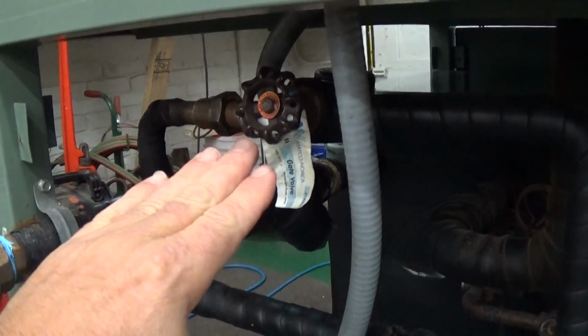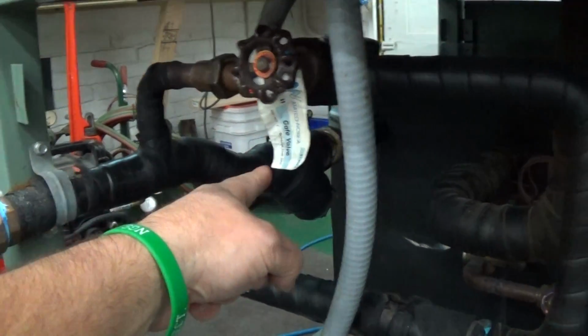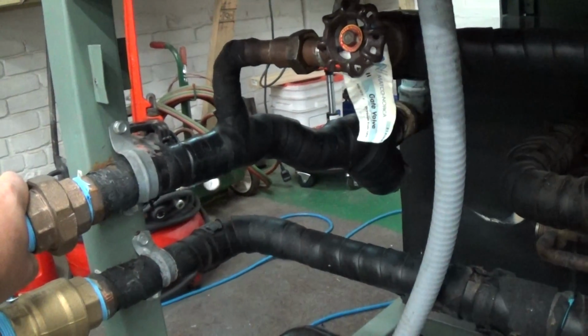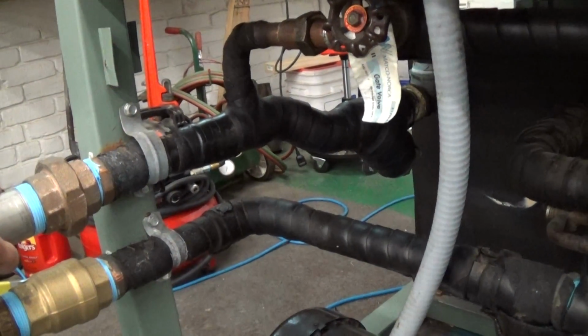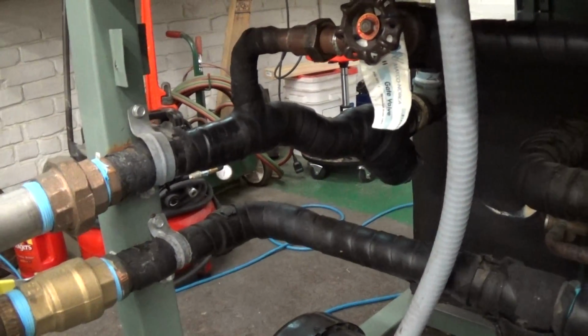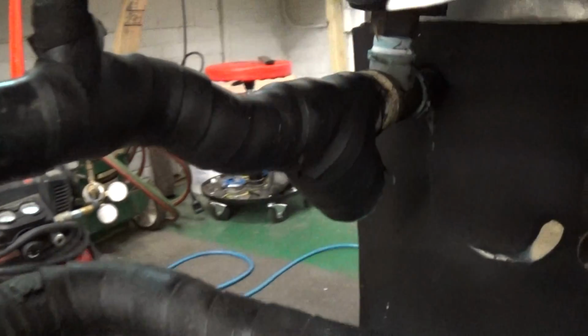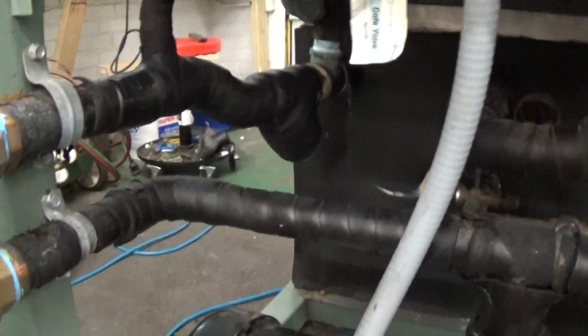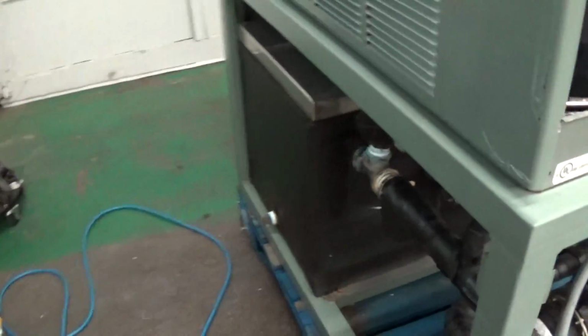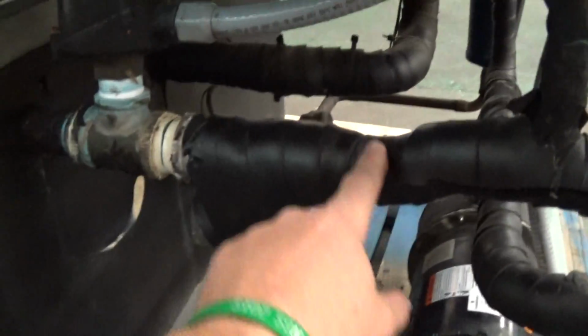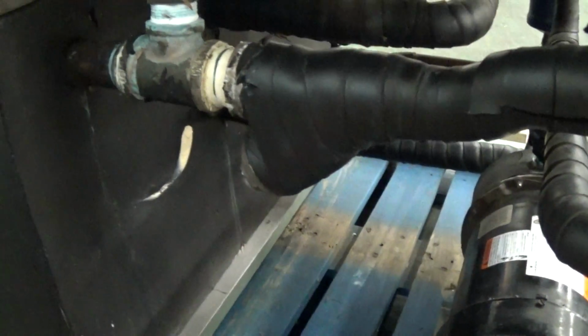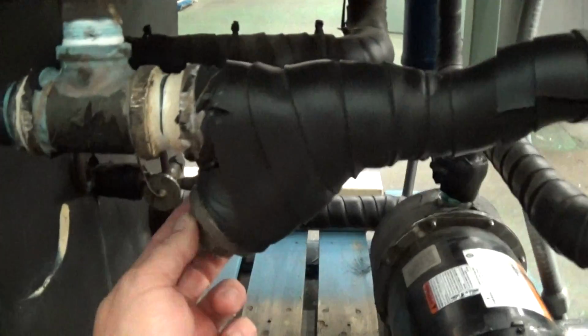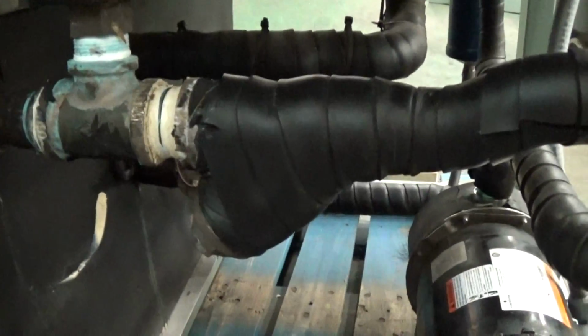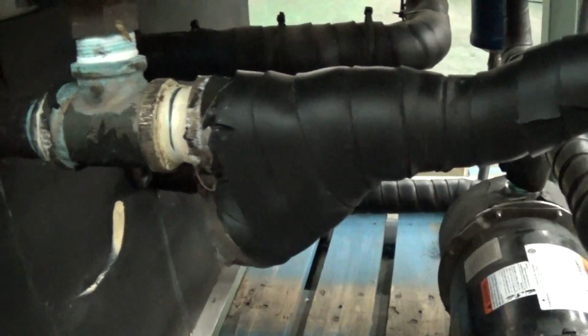What that does is that gives some additional flow back into the tank where the heat exchanger is, so we don't limit too much the amount of flow going over the heat exchanger, because there's a minimum amount of flow needed. Actually, while you're back here, you can see up above, that's the flow switch. That's the integrated flow switch for safety in the chiller. And now down below, this is called a Y strainer. That's basically a filter. Periodically, you should take this cap off here, and there's a little mesh screen there, and you check that for debris.